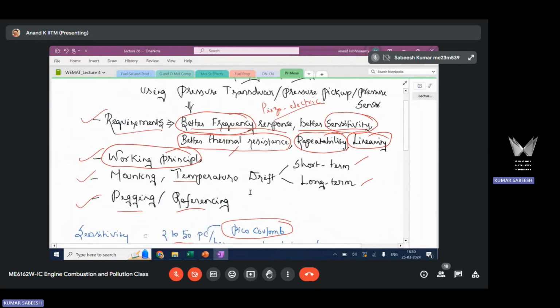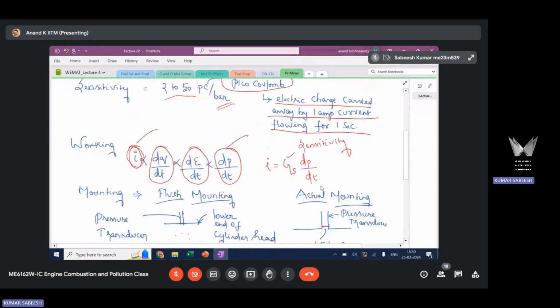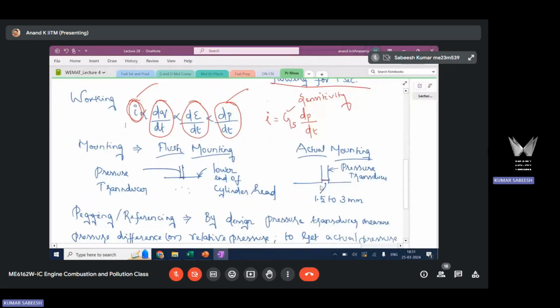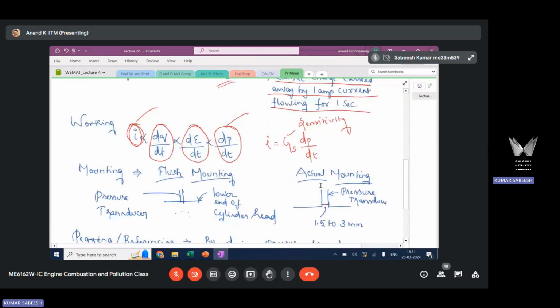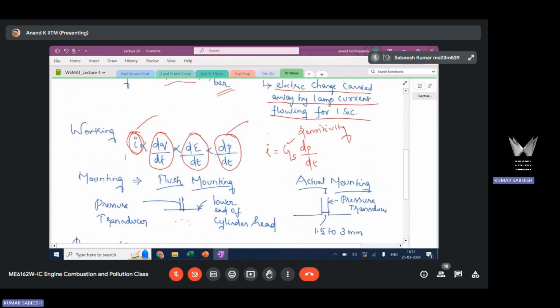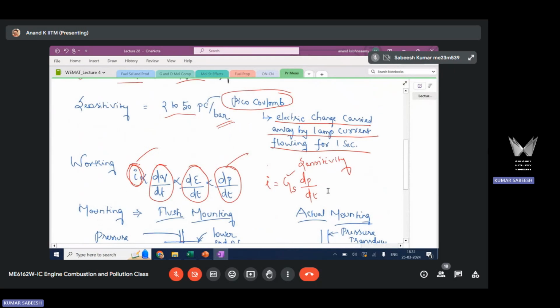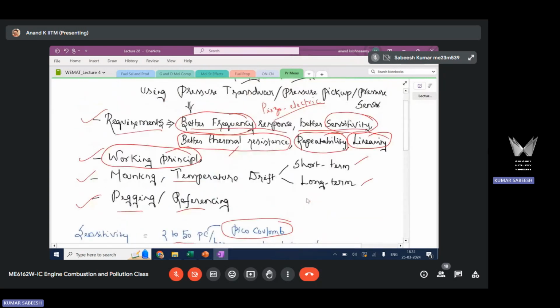Sir, this constant, sensitivity GS, seems to be a constant value in this equation. But in a practical sense, does it remain constant throughout the application? So how you will get this value is through calibration, as I said. Okay, sir. So you need to calibrate it at multiple points. With known applied pressure, you need to track the output voltage. And generally, as I said, we need to have a linear relation between the pressure and the electric signal. Thank you, sir. Thank you so much.